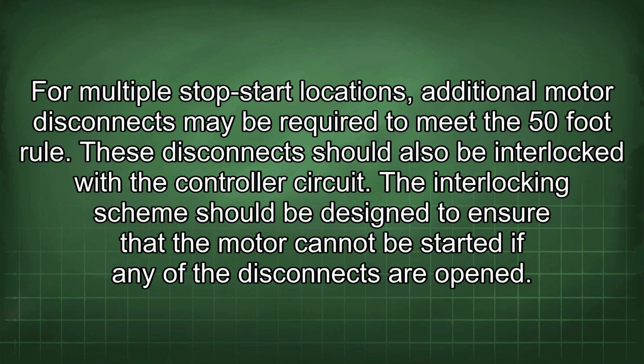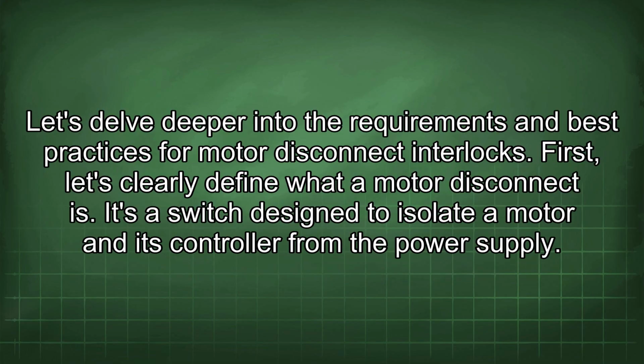For multiple stop-start locations, additional motor disconnects may be required to meet the 50-foot rule. These disconnects should also be interlocked with the controller circuit. The interlocking scheme should be designed to ensure that the motor cannot be started if any of the disconnects are opened. Let's delve deeper into the requirements and best practices for motor disconnect interlocks.